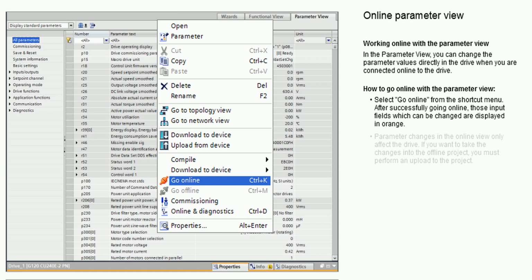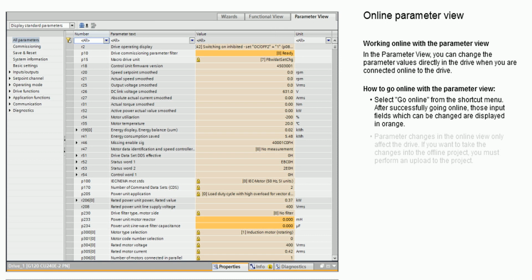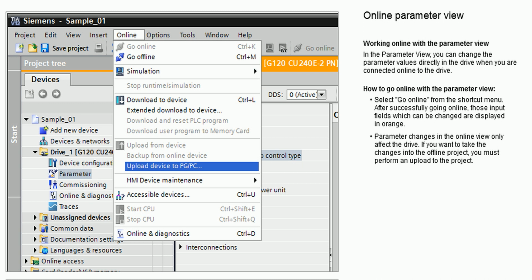After successfully going online, those input fields which can be changed are displayed in orange. Parameter changes in the online view only affect the drive. If you want to take the changes into the offline project, you must perform an upload to the project.